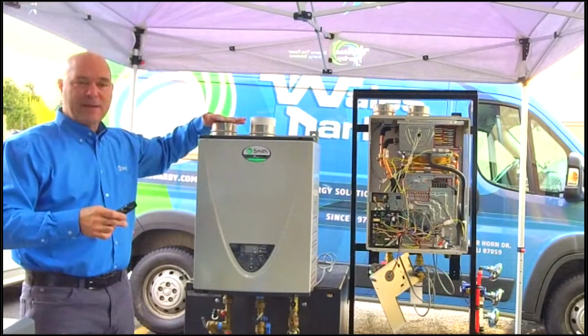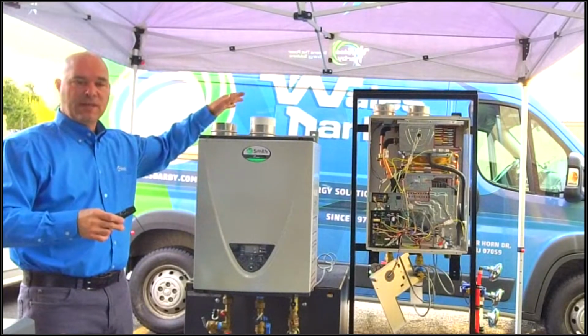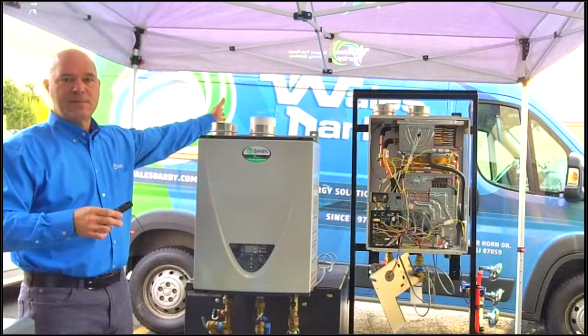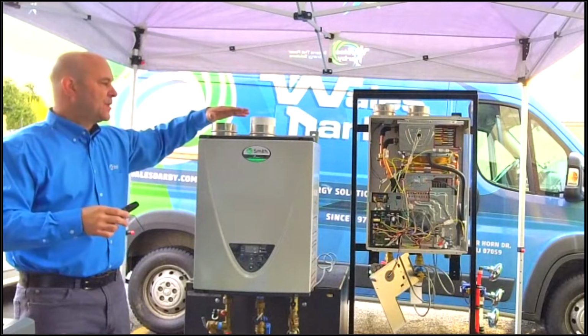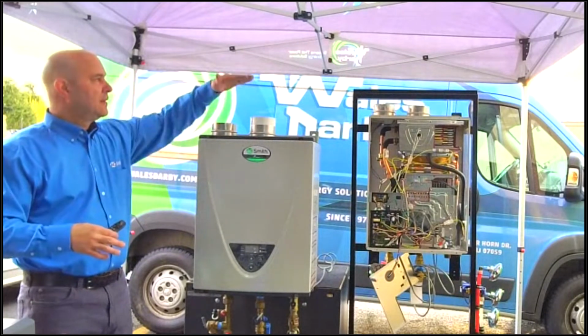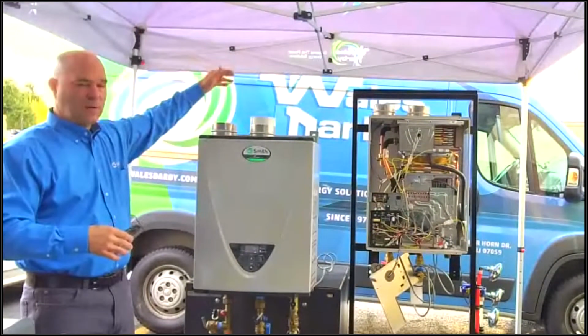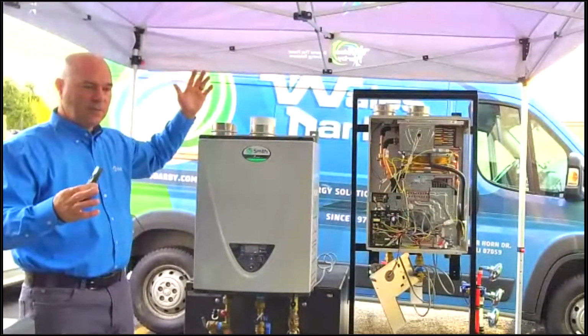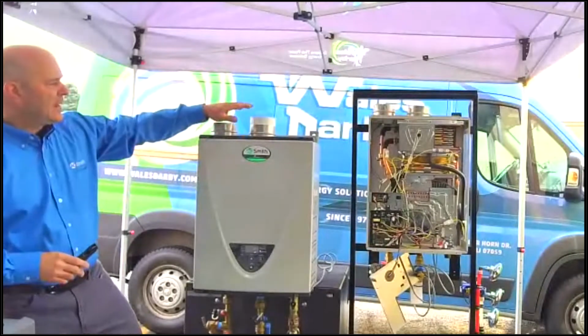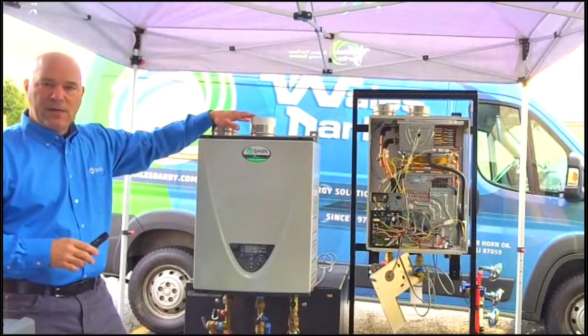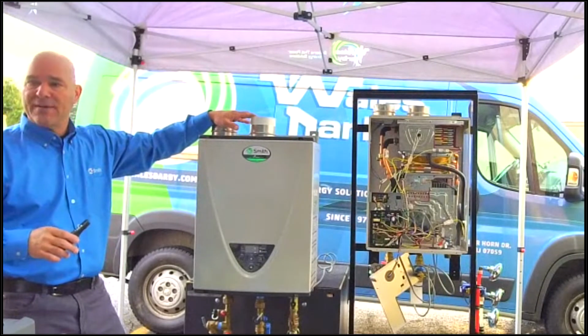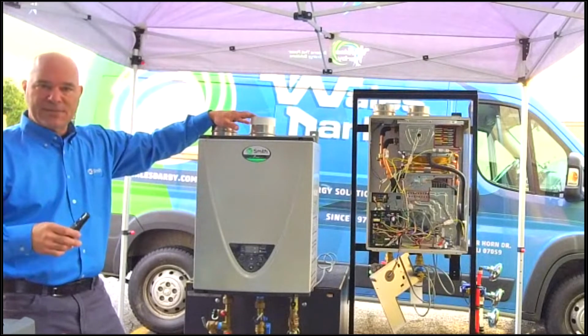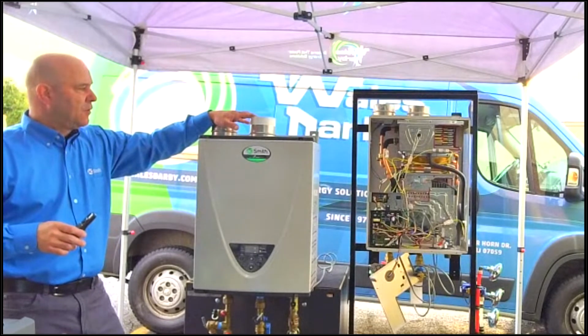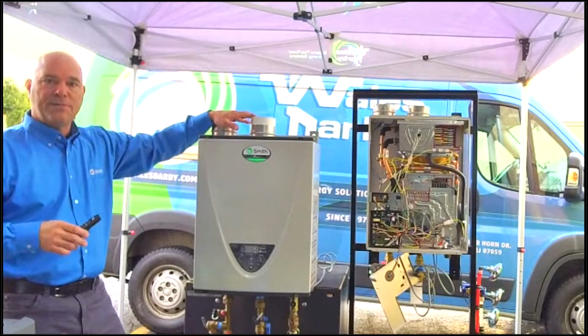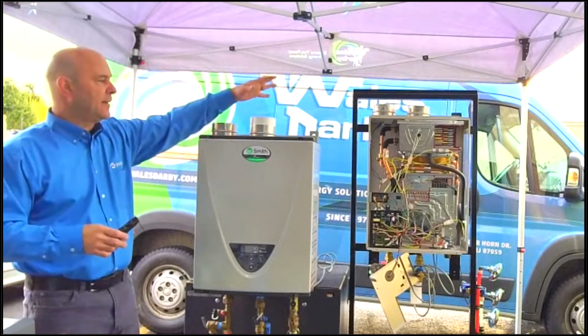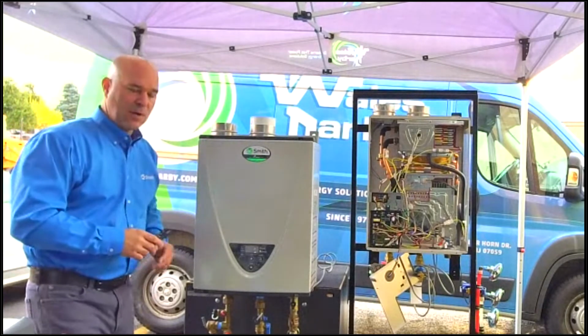If you don't have that, your best option is always to do 2 pipe. Best option is always to put them in the same atmospheric pressure zone and try to have like pipes. 1 elbow and out, 1 elbow and out, 2 elbows, 2 elbows, whichever it is. Again, 75 feet with 3-inch, depending on how many elbows you have. We usually limit this to 5 elbows, and you can go up to 100 feet with 4-inch pipe. So you come out of here, increase to the 4-inch, and make your runs.